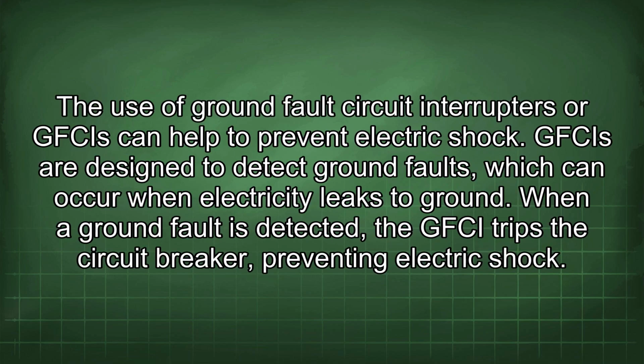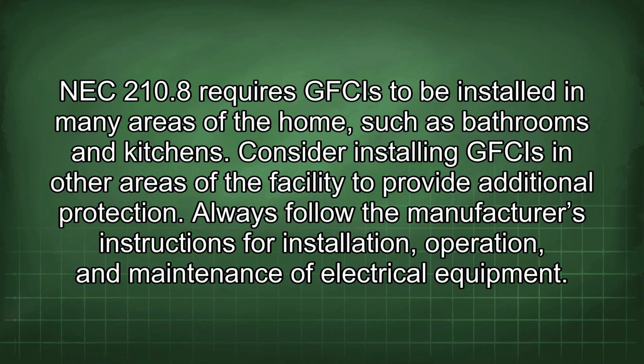The use of ground fault circuit interrupters, or GFCIs, can help to prevent electric shock. GFCIs are designed to detect ground faults, which can occur when electricity leaks to ground. When a ground fault is detected, the GFCI trips the circuit breaker, preventing electric shock. NEC 210.8 requires GFCIs to be installed in many areas of the home, such as bathrooms and kitchens. Consider installing GFCIs in other areas of the facility to provide additional protection.